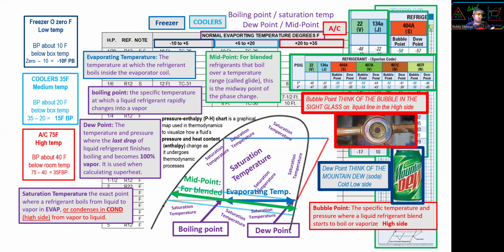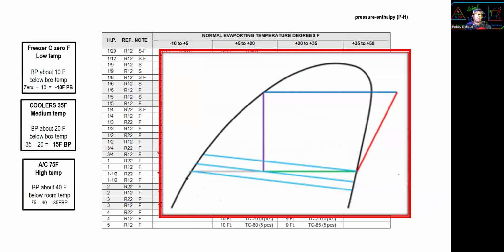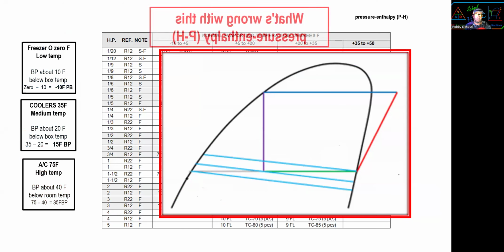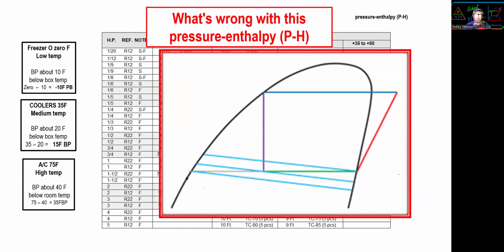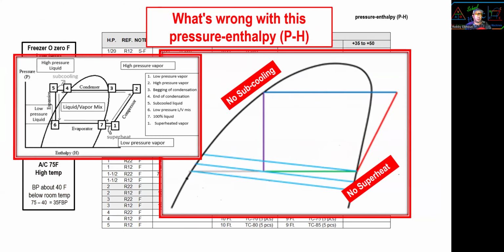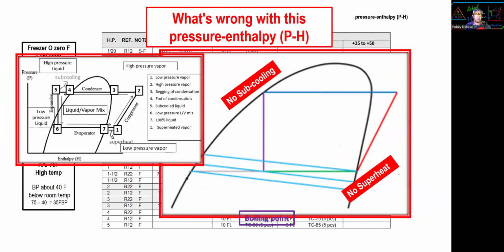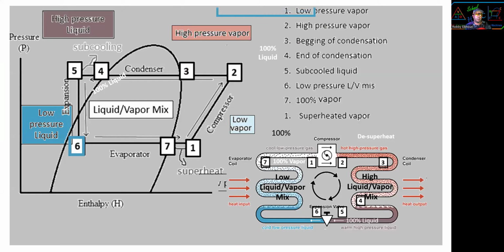Okay, but something's wrong with my slide. What's wrong with my pressure enthalpy chart? No superheat and no subcooling. This is the proper chart, and since we're here, let's cover it. Boiling point, dew point. Now we start with the low pressure vapor mix, number 6. That's your boiling point. Cold, low pressure liquid.